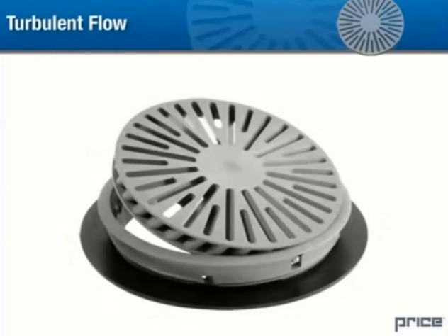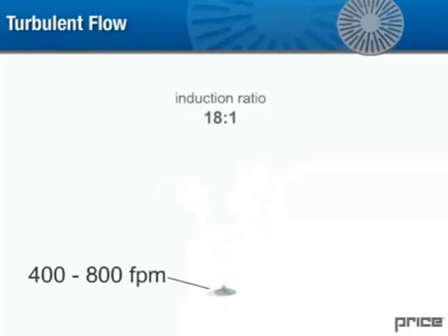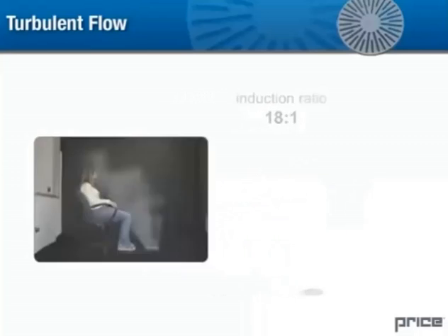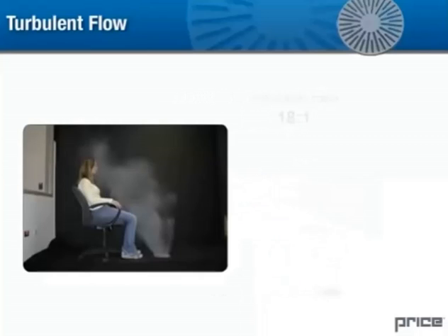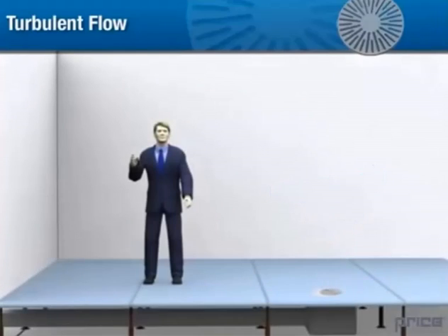An underfloor air distribution system uses floor twist outlets to generate a turbulent airflow. These turbulent flow diffusers discharge conditioned supply air at elevated velocity, around 400 to 800 feet per minute, at floor level. The discharge is a vertical swirling pattern which rapidly induces the room air. This turbulence enhances the induction of room air and allows occupants to be in close proximity to the supply air jet without feeling drafts.